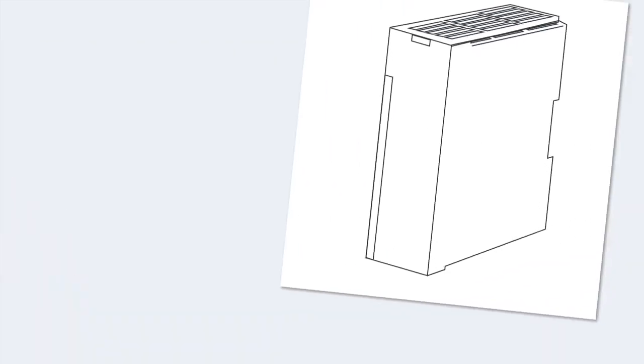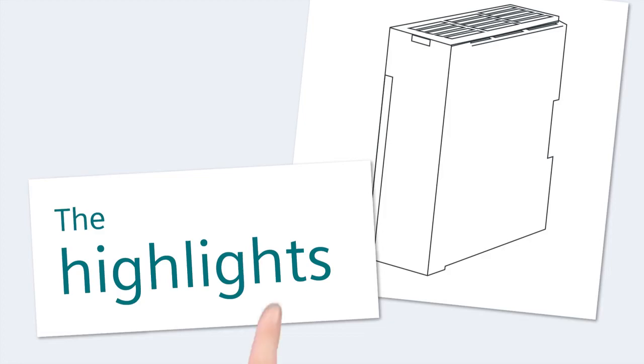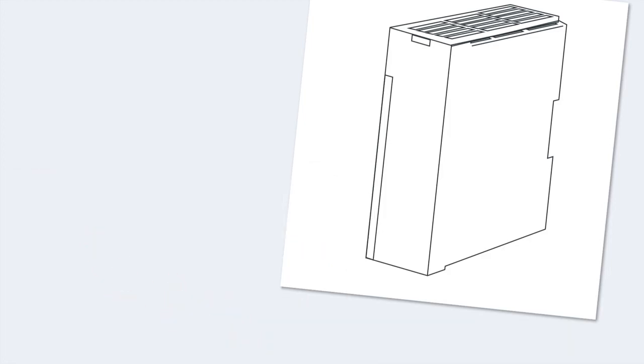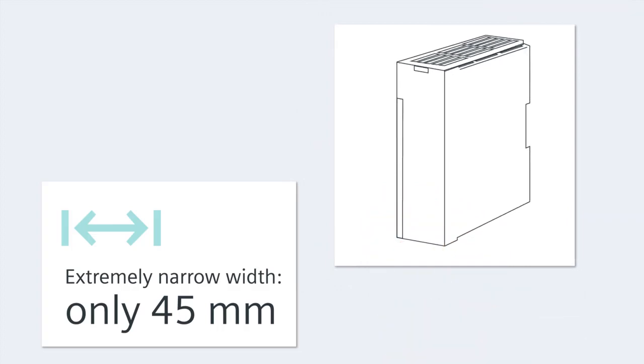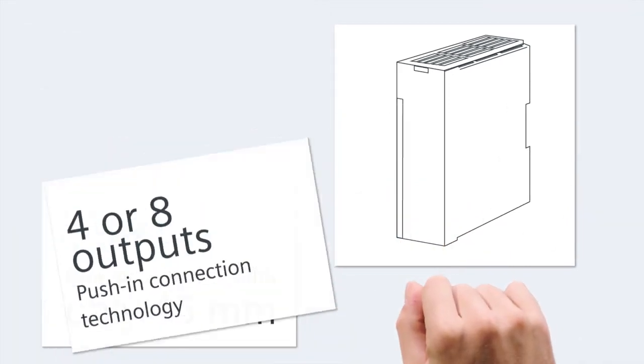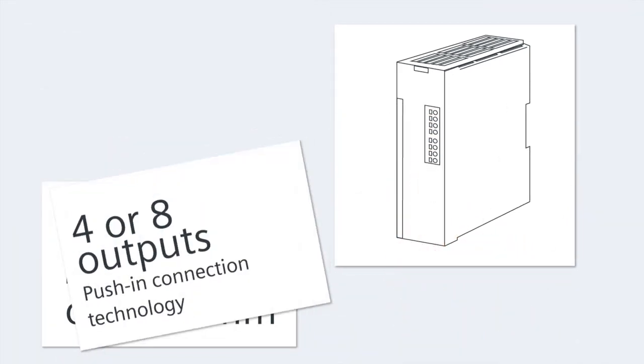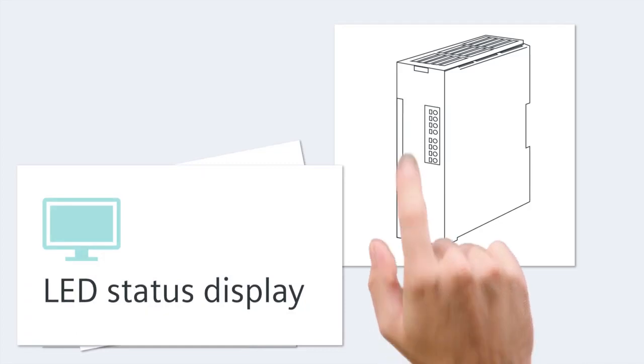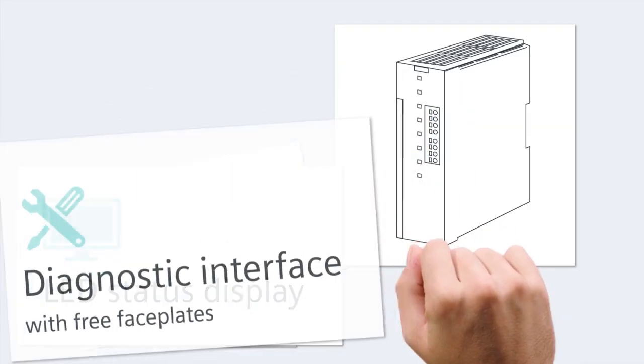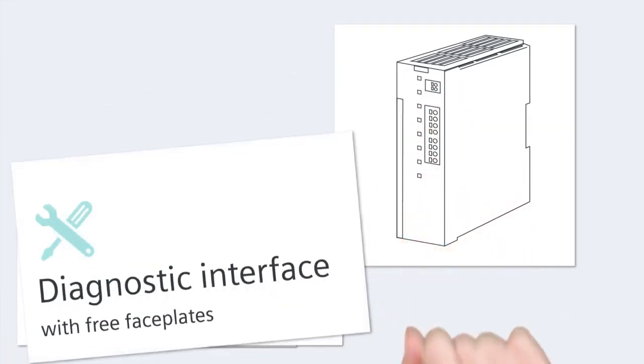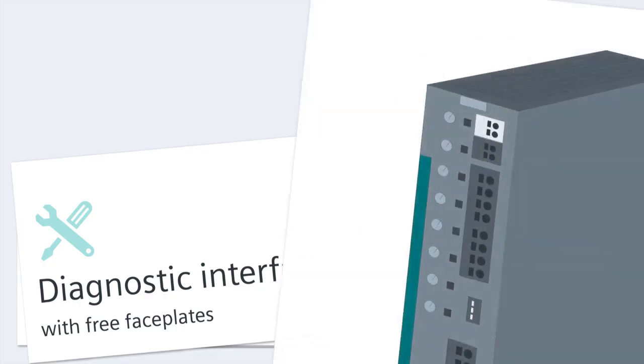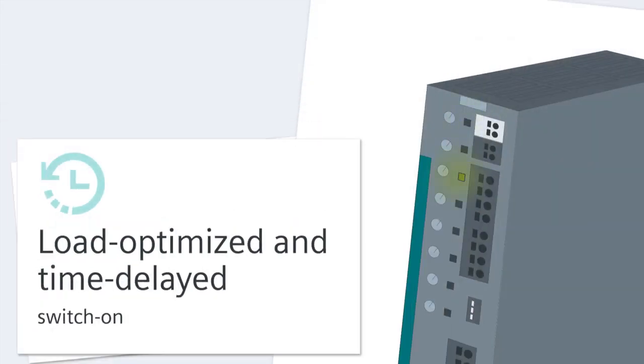Let's start with the highlights of the new SITOP selectivity modules. They have an extremely narrow width of only 45 millimeters, four or eight outputs that can be set between 2 and 10 amperes, push-in connection technology, an LED status display, and a diagnostic interface with free faceplates. They also permit load-optimized and time-delayed switch-on.